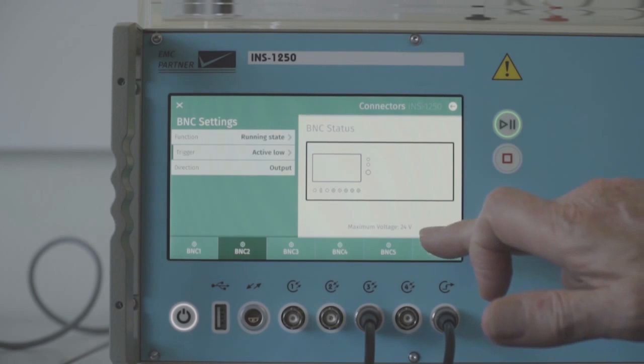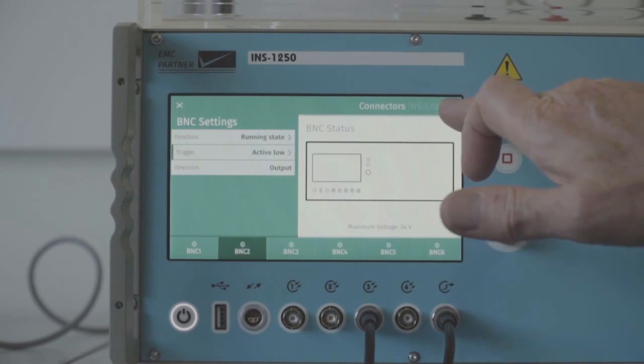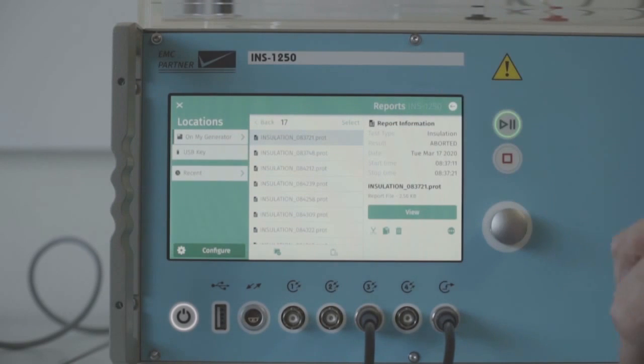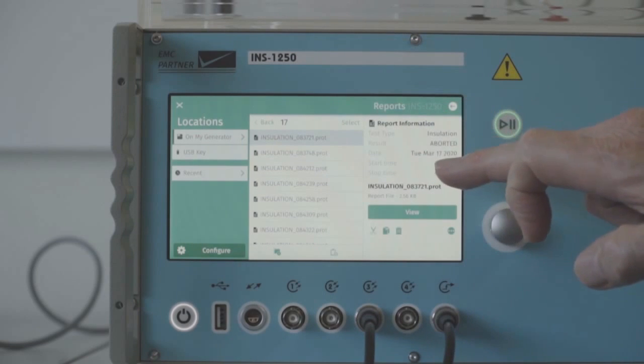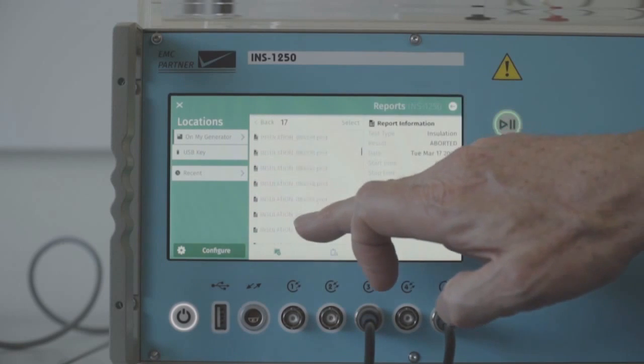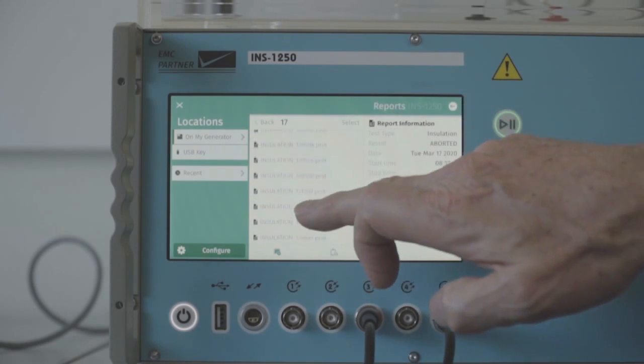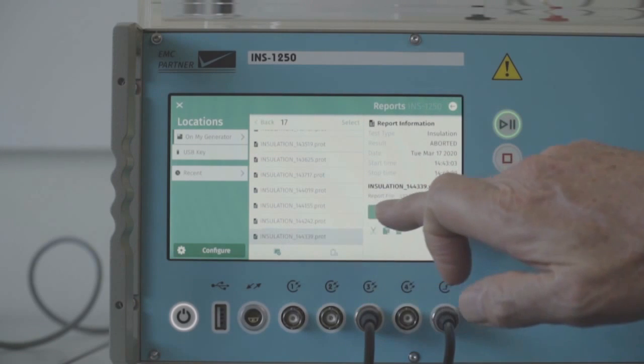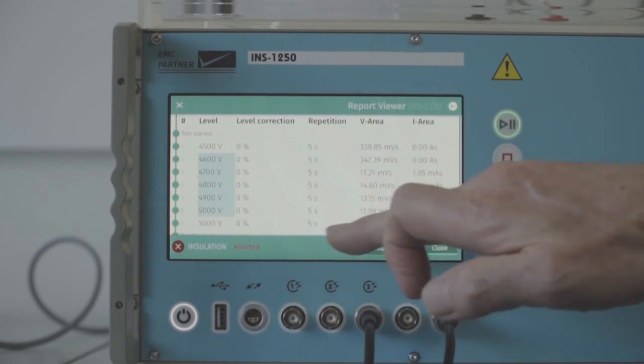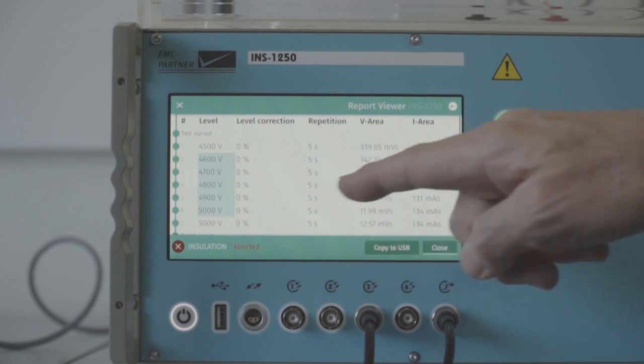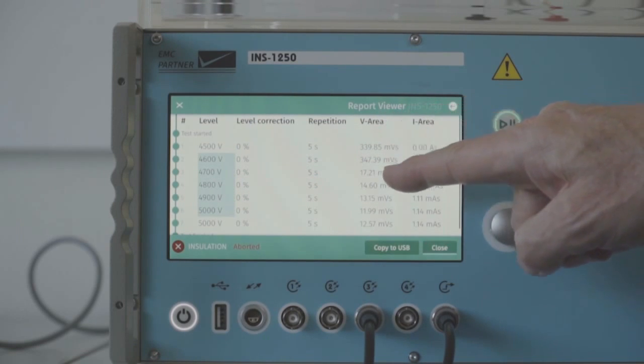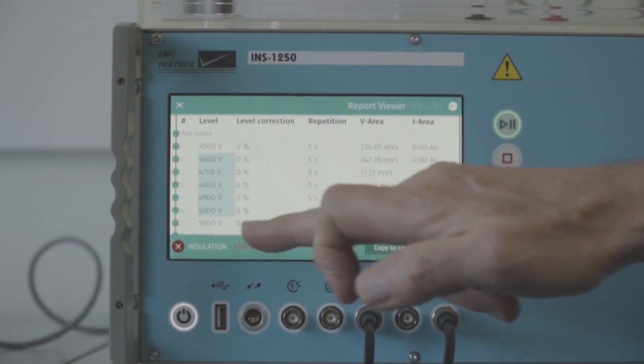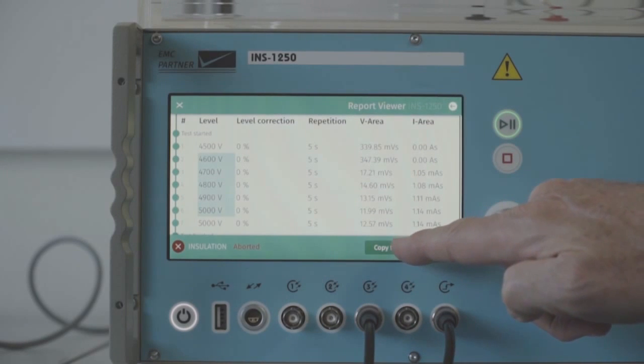Finally, in the generator we have the reports which are produced during the test processes. Inside the generator is a library of the test reports. We can store all of the reports that were taken within the library. Select and we can view. So here is a report where the voltage was increasing using the ramp function, and we see the voltage integral and the current integral as the test progresses. This report can be exported from the generator through the USB port.